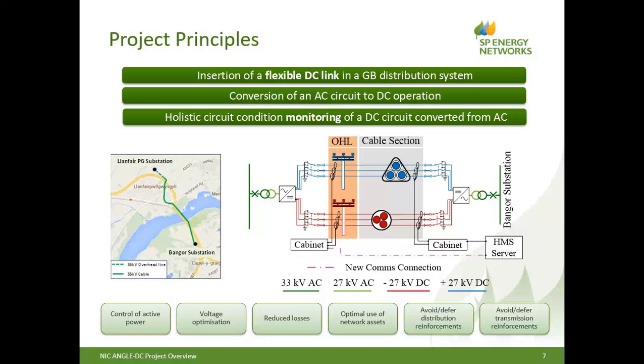Obviously, that brings into play a number of other points to consider, such as transient faults, which will occur from time to time. This area is quite exposed, and lightning strikes and storms are quite the norm. You can see on the diagram on the right hand side the two poles, so you can see the two circuits between the substations. There'll be a transformer, the MVDC converter, thyristor bank. It then splits into the two poles.